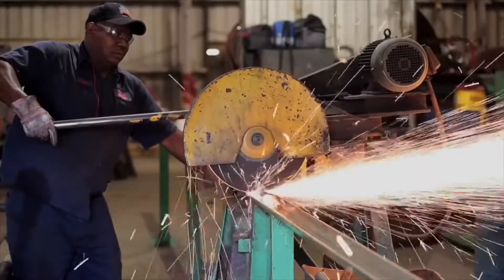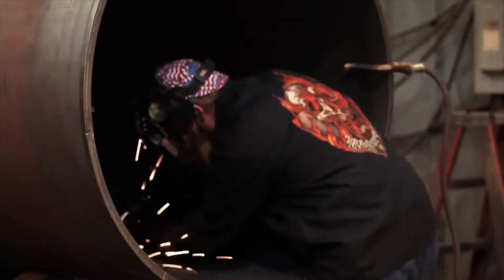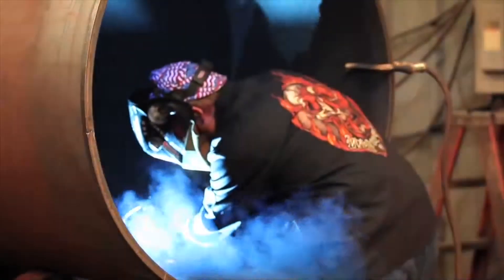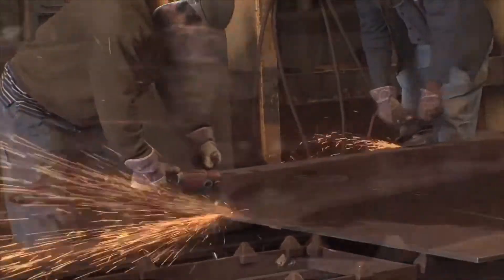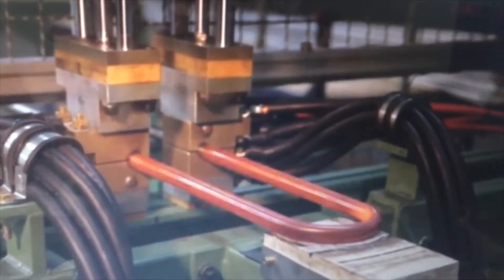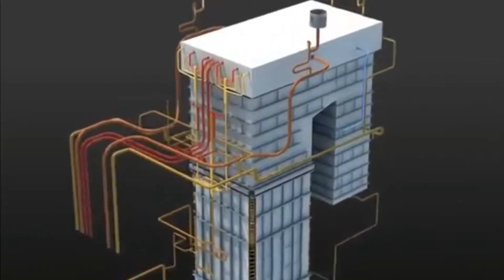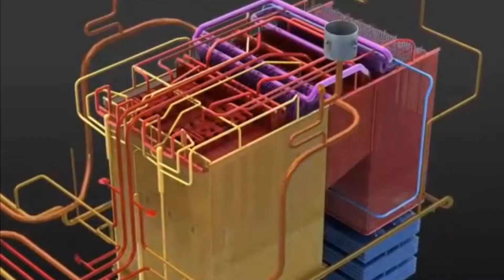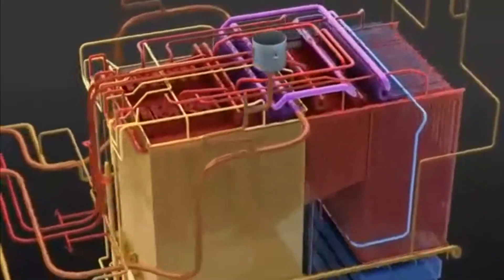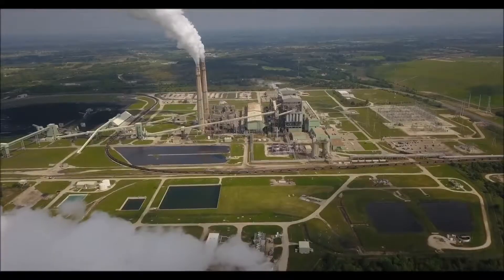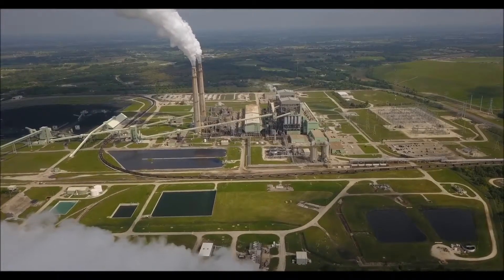Water tube boilers have more complex designs and manufacturing techniques than fire tube boilers, but they have one main advantage: almost no design limitations for steam production loads. The advancement of material technology and metal welding means water tube boilers can be built as large as possible. Therefore, water tube boilers are more suitable for large industries requiring high quality and quantity of steam, such as power plants.